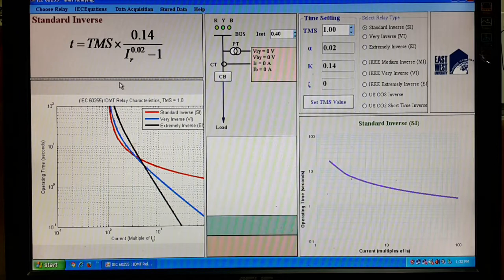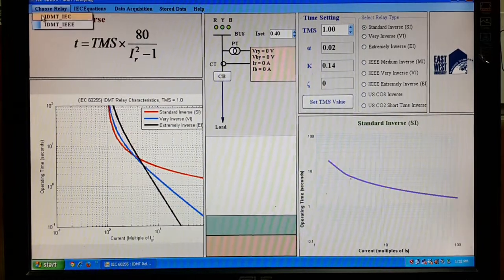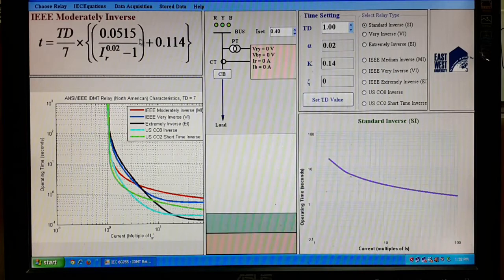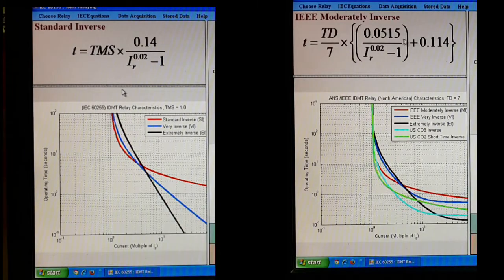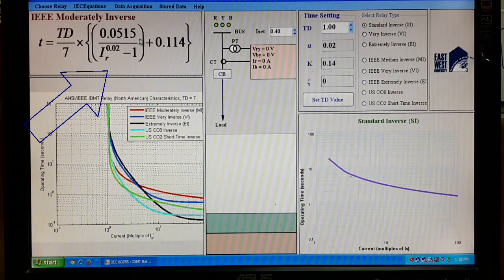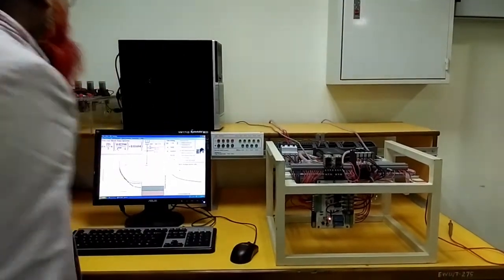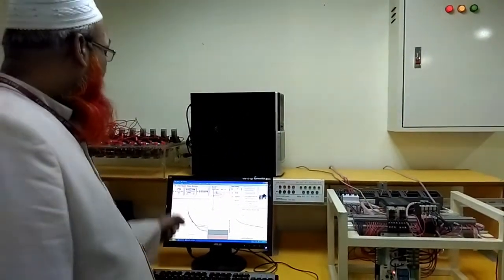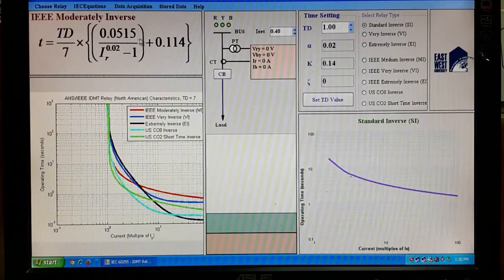If you want to see the IEEE characteristic curves, you can see the equations here. In IEC and IEEE, the terminologies are different: IEC uses TMS (time multiplier setting) and IEEE uses time delay. The curves and equations are shown on the left side for learning. On the right side the same equations are implemented, but you can change the parameters — on the left side you cannot.